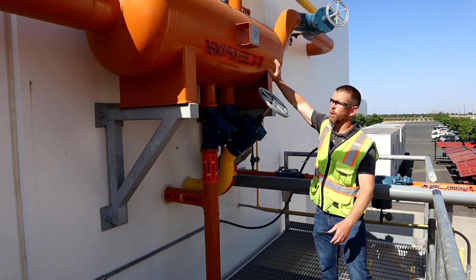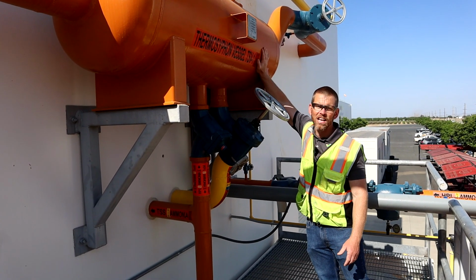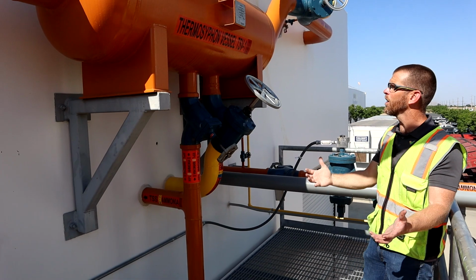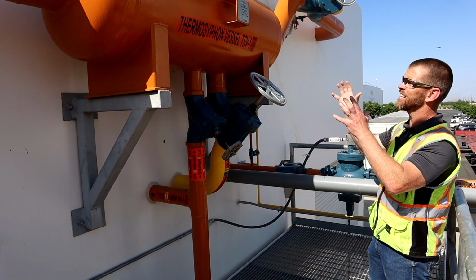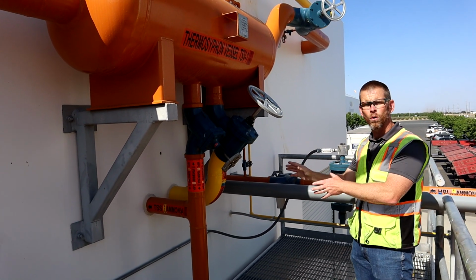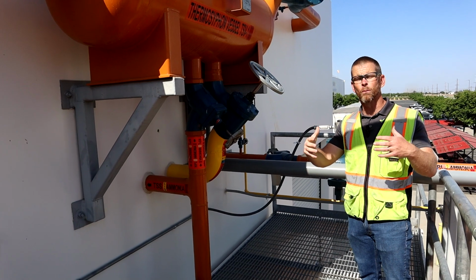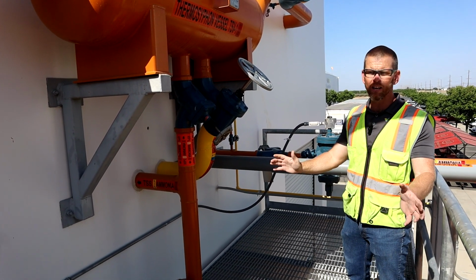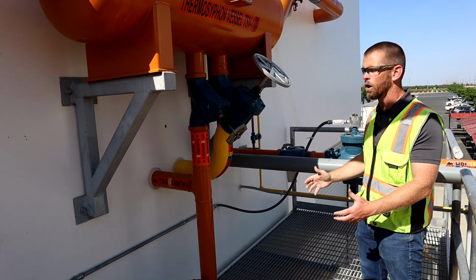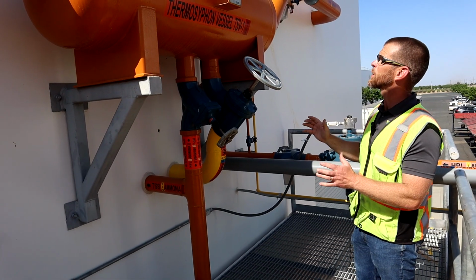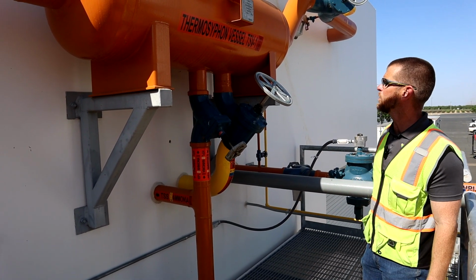All right, this vessel here that we're looking at is a thermosyphon vessel. Sometimes it's called a thermosyphon receiver. And what it does is it supplies liquid to the oil coolers on screw compressors that are thermosyphon oil cooled. Not every compressor is thermosyphon oil cooled, but some are. In this system, they are. So it's a great opportunity to do an overview of that.